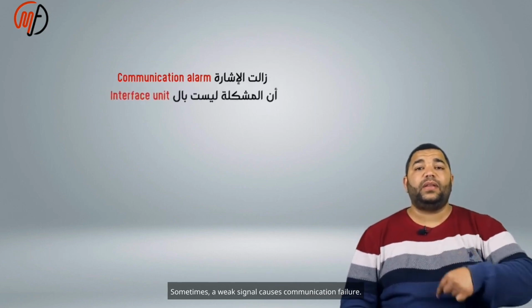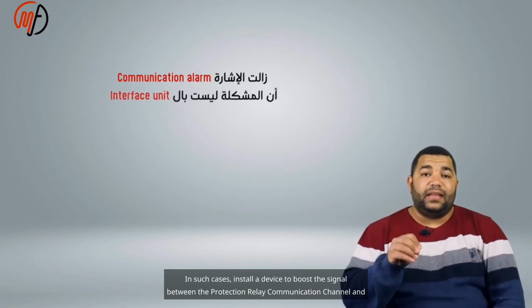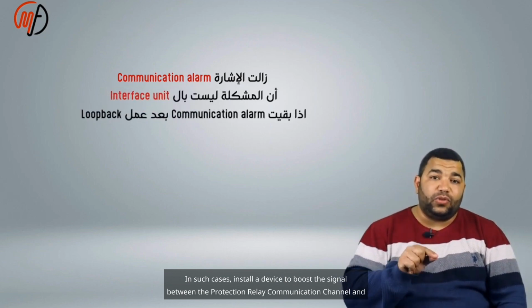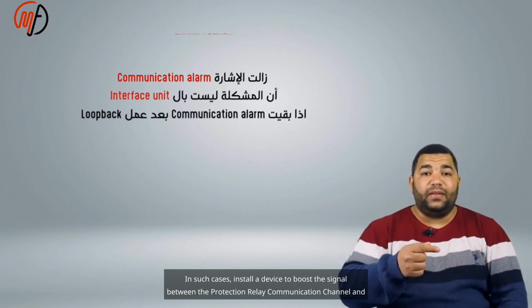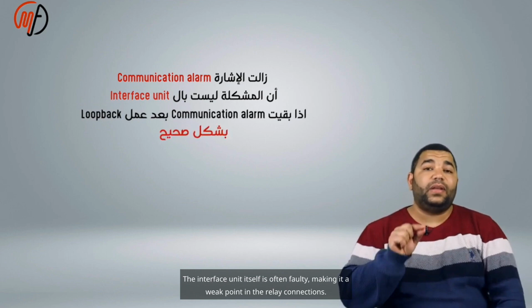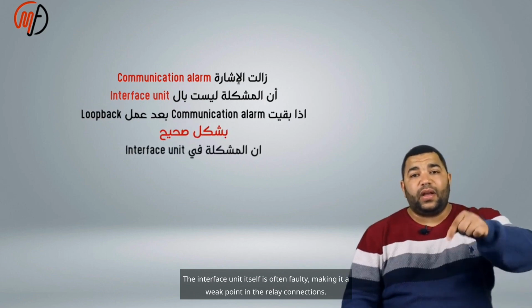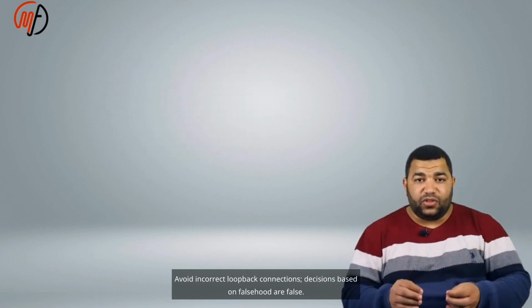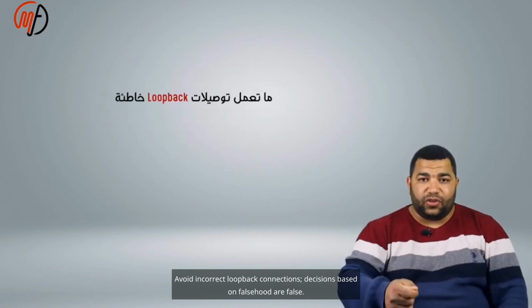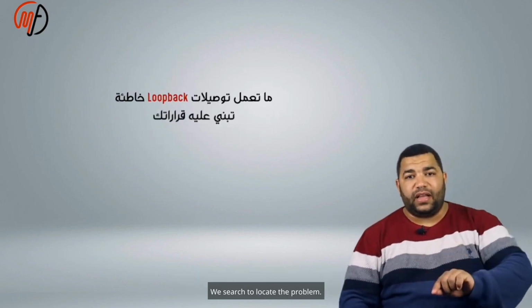Sometimes a weak signal causes communication failure. In such cases, install a device to boost the signal between the protection relay communication channel and the fiber optic cable. The interface unit itself is often faulty, making it a weak point in the relay connection. Avoid incorrect loopback connections. Decisions based on falsehood are false. We search to locate the problem.